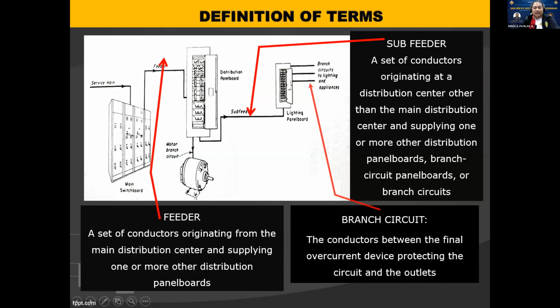Then eventually pag nandun na tayo sa main, sa dulo na talaga, which is doon nakakonect yung main power supply natin. So the conductors connecting that main switchboard to the first distribution panel board is what we call the feeder conductors. Okay? And then, yung conductors going outside, either connected na to the service utility or to a transformer, no? Ito yung tawag na service mains. Okay? So importante yan to know them para ma-designate natin properly yung load schedule natin.